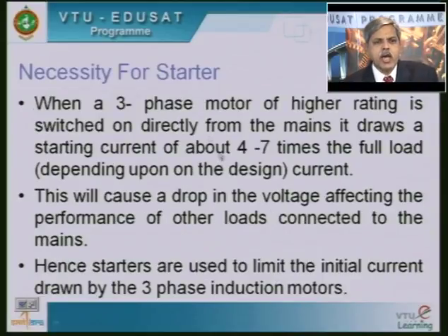See, all the motors require a starter. Now, what is the necessity of a starter? When a 3-phase induction motor of higher rating is switched on directly from the mains, it draws a starting current of about 4 to 7 times the full load current, depending on the design of the induction motor.